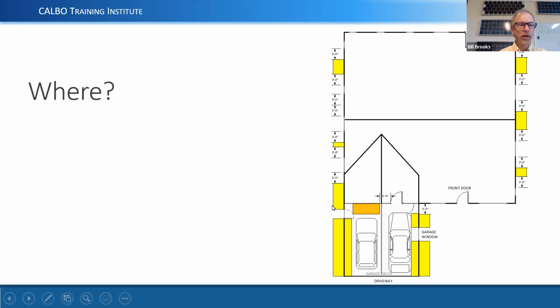Okay, so what I did is I actually took my house and I showed where, because of these rules, the yellow places are places that would be acceptable, more than 3 feet from openings into the dwelling unit. And so what you find out is that the main part of the dwelling unit, this square, is where your bedrooms and living rooms and dining room, kitchen, all that kind of stuff are. The only places you could actually legally install an energy storage system on the outside of the house would be here, here, up here in the top left, a tiny little space, not big enough to install anything there. And then as you come off of the garage, there's a larger space right there.